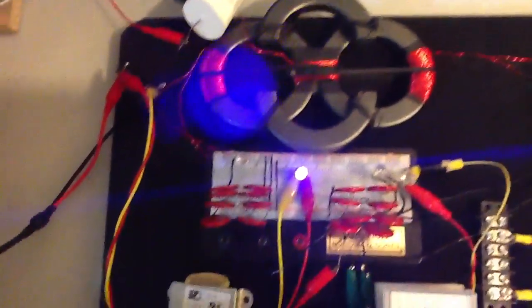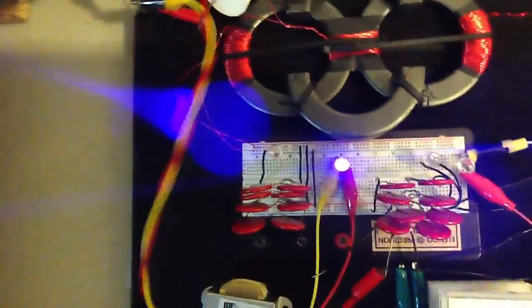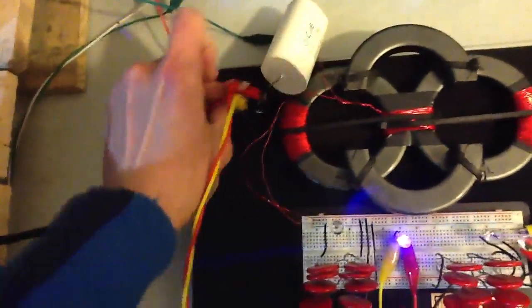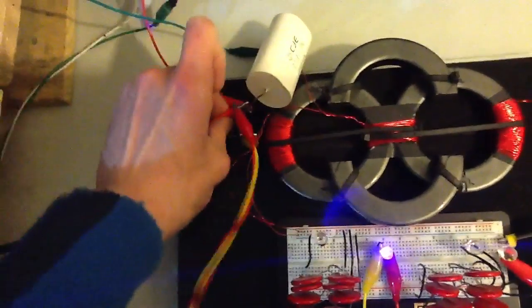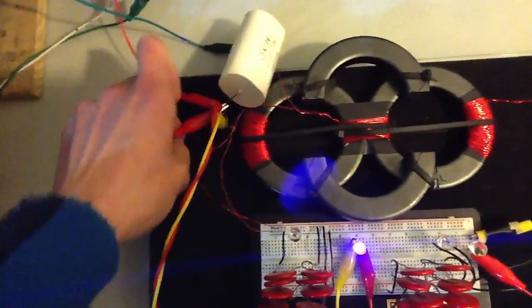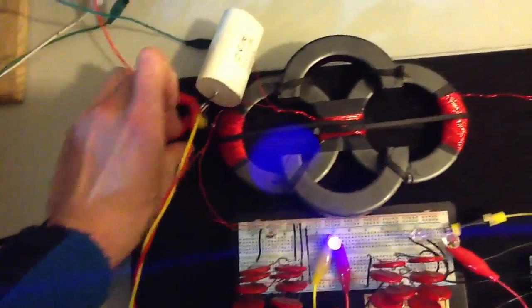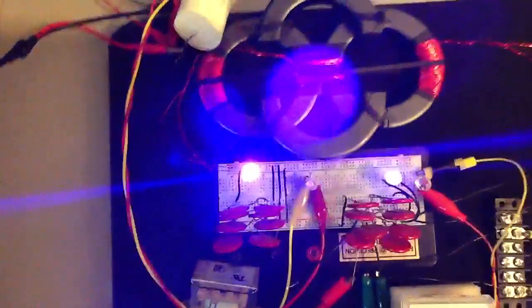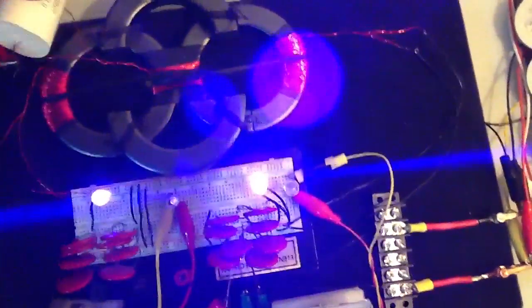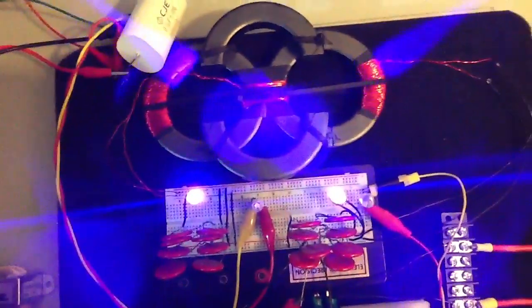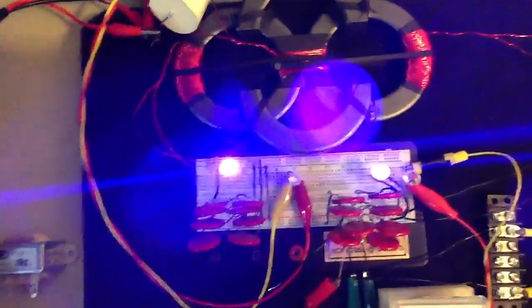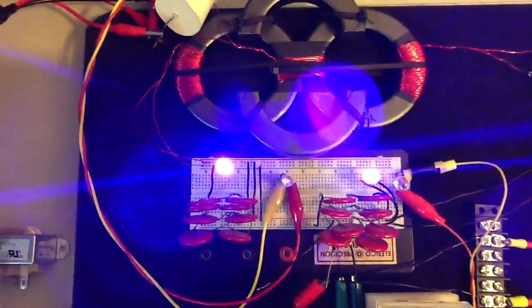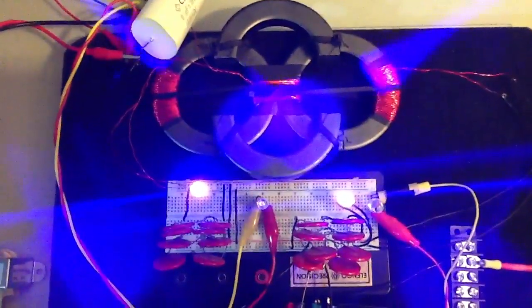I'm going to adjust some things. So here you can see, when the biotoroid goes on load, the primary decreases, and both secondaries become very active.